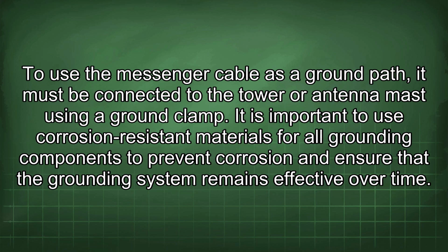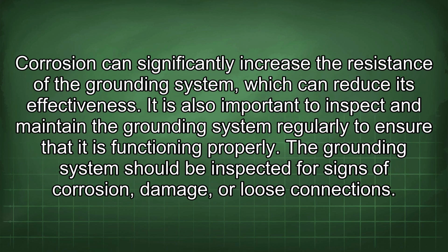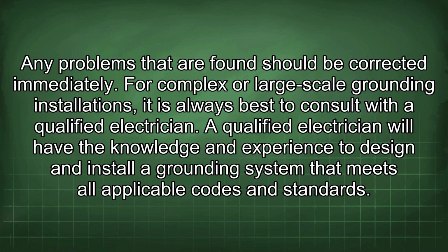a ground clamp. It is important to use corrosion-resistant materials for all grounding components to prevent corrosion and ensure that the grounding system remains effective over time. Corrosion can significantly increase the resistance of the grounding system, which can reduce its effectiveness. It is also important to inspect and maintain the grounding system regularly to ensure that it is functioning properly. The grounding system should be inspected for signs of corrosion, damage, or loose connections. Any problems that are found should be corrected immediately.